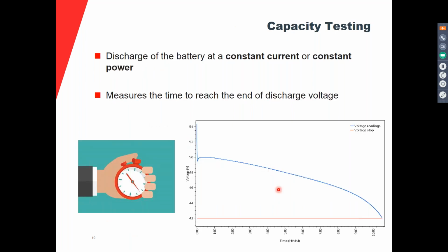So if you have a battery that is 60 cells and the end voltage is 1.75, it means that you need to run the test down to 105 volts. And if you have a 24 cell battery, a VLA battery, then you have 24 cells times 1.75, that means you need to run the battery down to 42 volts, like in this example. And once the battery reaches that point, we have the time, and we also stop the test. The test has to be stopped there. The voltage cannot go beyond that. If not, the cells will be affected in their chemistry and capacity, and probably won't be able to recover that.